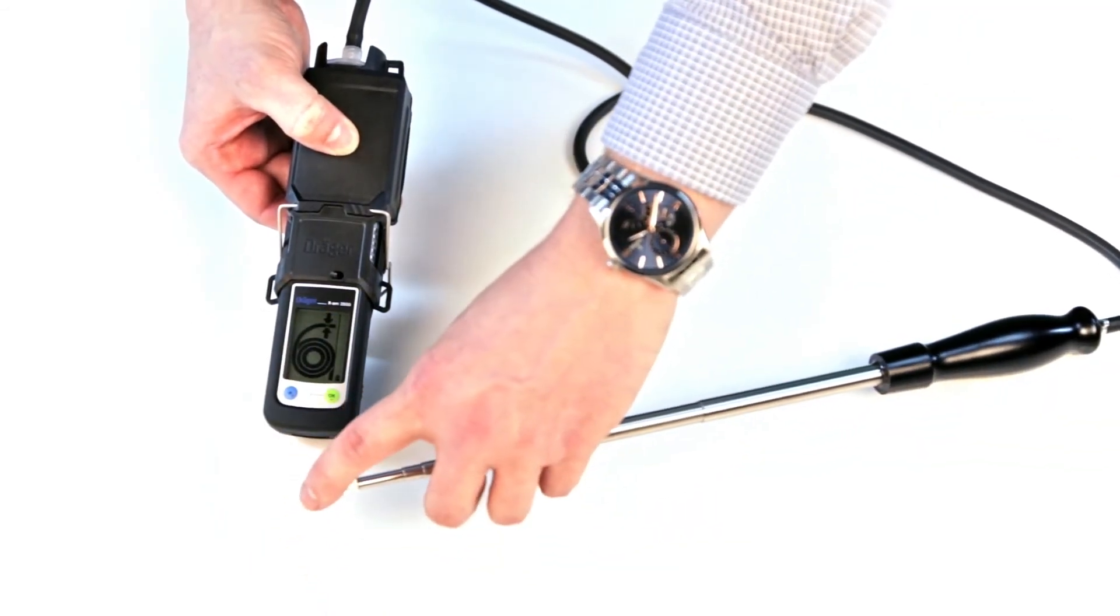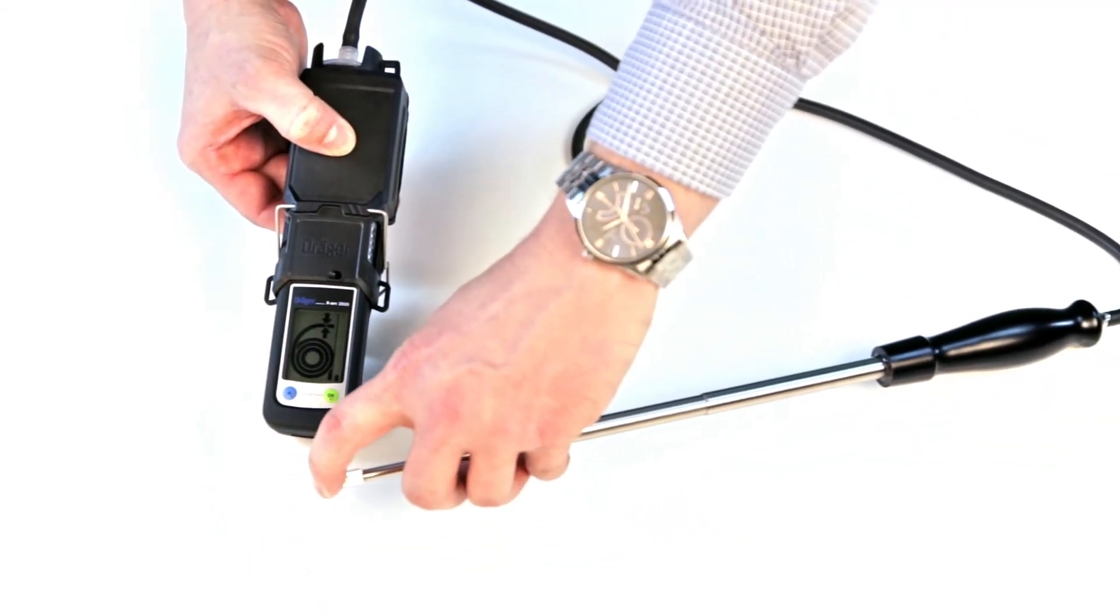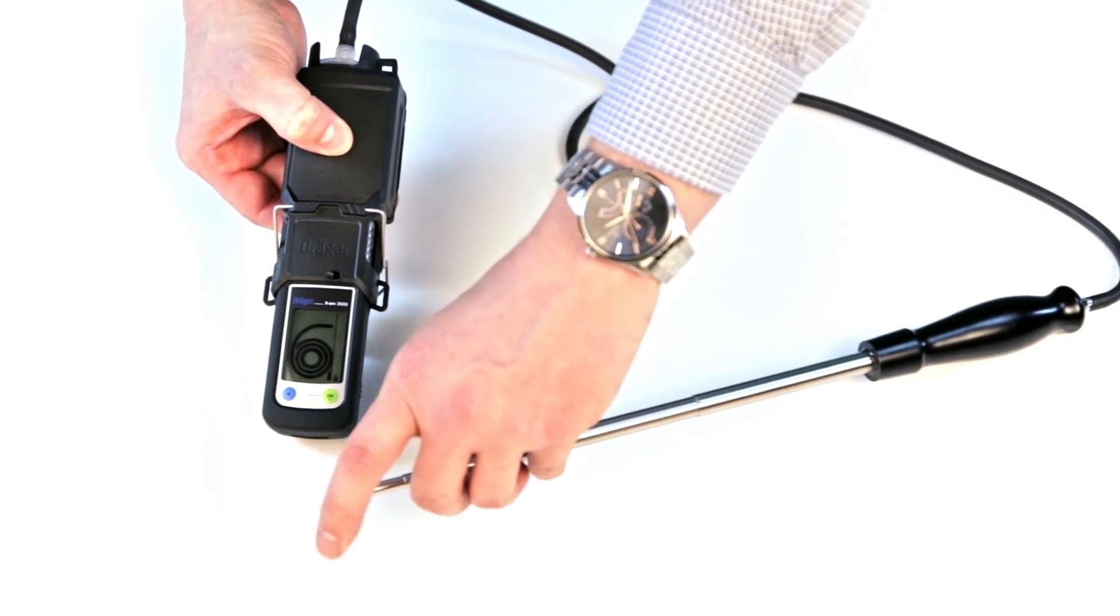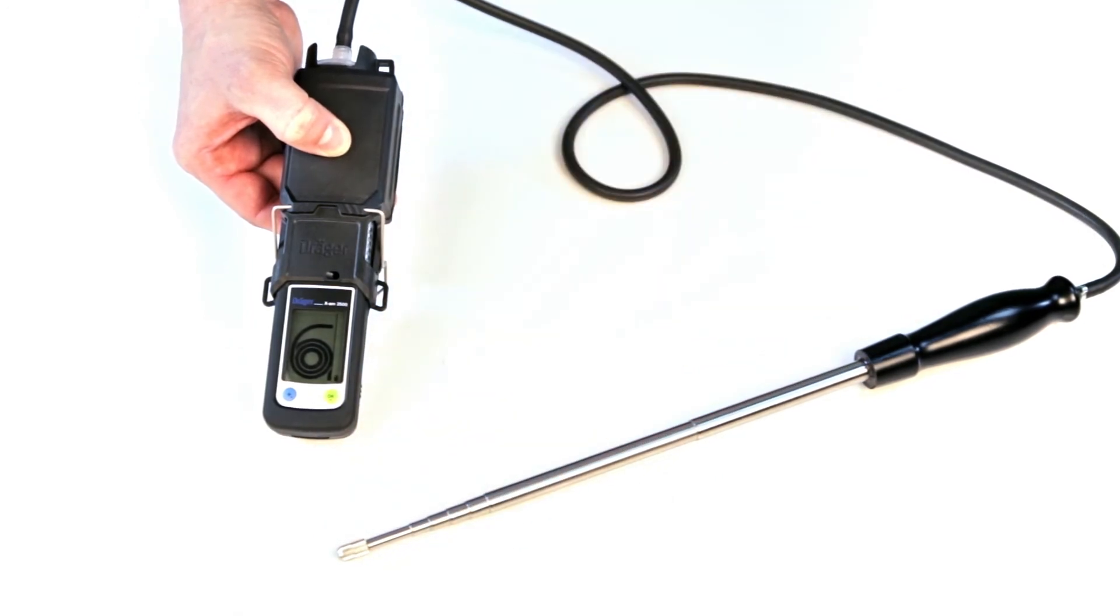To check the flow of the pump, block the end of the hose or probe with your finger. When the system is tight, the pump will stop. If the flow check is completed successfully, the open symbol is shown and the pump will start again.